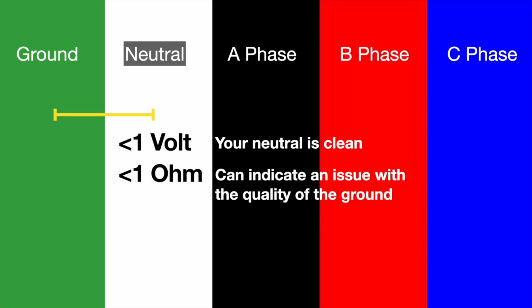Keep in mind, the less than 1 volt reading between ground and neutral is only valid if nothing in your system is on. Best practices are either to have all your breakers off or to have nothing terminated into your distro, amplifiers, console, anything like that, while you're measuring this.